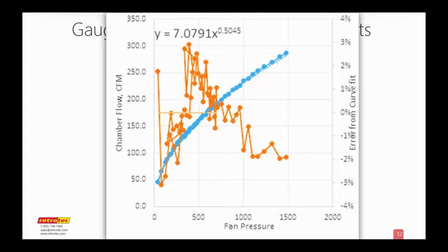You said that as far as EQLA was concerned, or you're measuring hole size, both the DM2 and the DG700 will do that. And on the DM2, we call it EQLA for equivalent leakage area, and that's the size of a hole in a flat plate. There's unfortunately another ELA which has the same designations, and we call that the EFLA, the effective leakage area, and it's 0.61 times that leakage area.